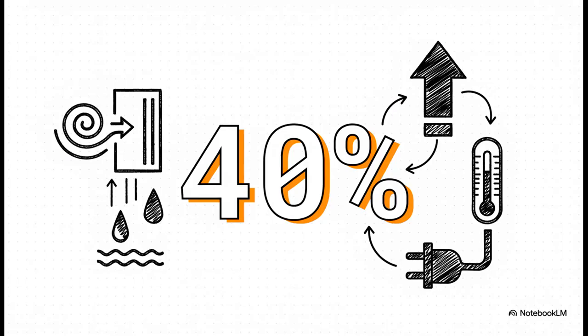Okay, so here's the core problem. Fresh air is incredibly expensive. I mean, think about it. In humid climates, just cooling and dehumidifying the outside air you have to bring into a building can eat up a staggering 40% of its entire energy load. That is a massive, constant drain on power. It's basically like leaving a giant window wide open 24/7, but for your building's entire energy bill.